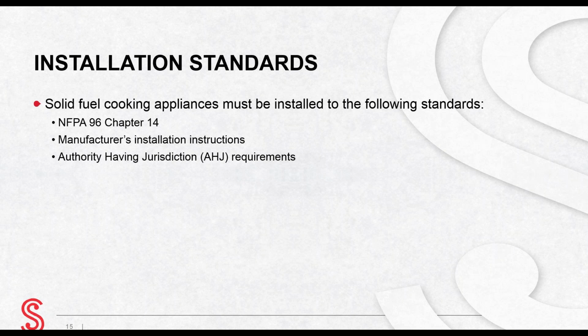NFPA 96, Chapter 14, Solid Fuel Cooking Operations, provides the safety requirements for solid fuel cooking. These include exhaust venting, location of the appliance, air movement, fire extinguishing equipment, procedures for inspection, cleaning, and maintenance of the appliance, as well as the minimum safety requirements for fuel storage and handling and ash removal. The manufacturer's installation instructions are sent with your new ovens or can be obtained from the manufacturer if you purchase a used oven. They must be followed for the safe operation of the oven and to prevent meat smoking fires.